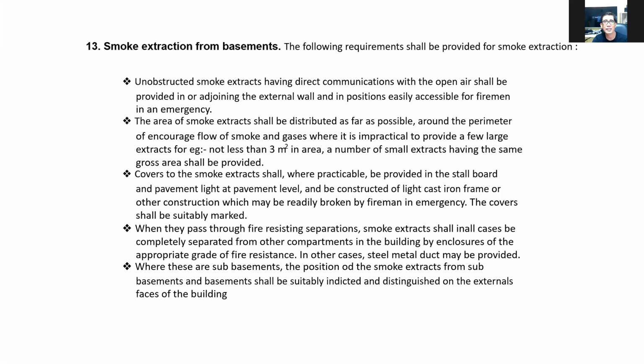Okay. Another one: when they pass through a fire-resisting separation, smoke extraction shall in all cases be completely separated from other compartments in the building by enclosures of appropriate grade of fire resistance. In other cases, sheet metal ducts may be provided. Where there are sub-basements, the position of the smoke extracts from sub-basements and basements shall be suitably indicated and distinguished on all external faces of the building.